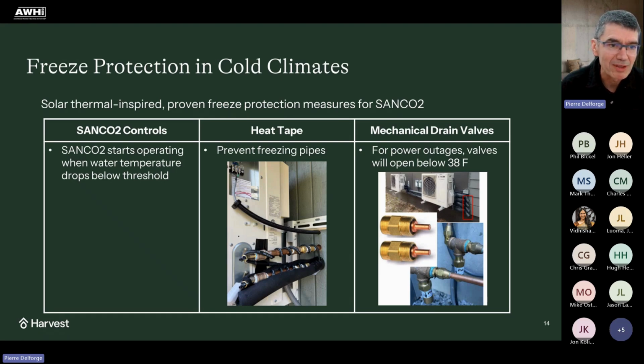Heat tape prevents pipe freezing, and importantly, even though power outages aren't frequent, they do happen, and we want to make sure the heat pump can survive power outages. That's done through a set of mechanical drain valves that don't need power and will basically circulate the system by opening up when the water drops below a certain threshold. It pulls warm water from inside the building, from the tank or the plumbing, to prevent freezing. Then once that warm water comes, the valve shuts off, until power is restored or the water gets cold again.